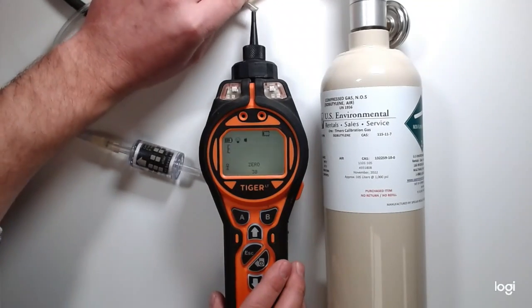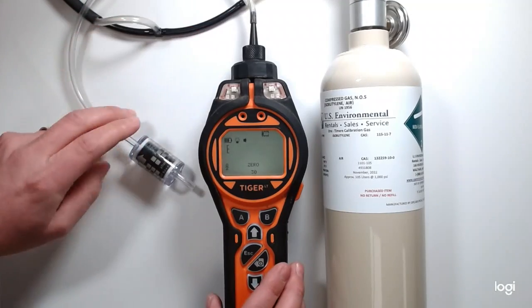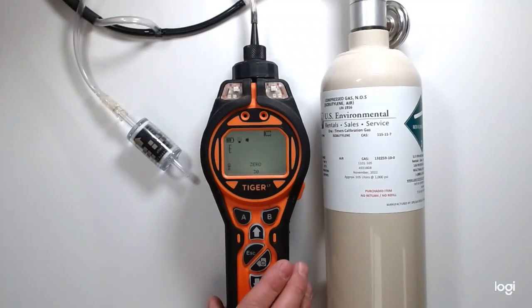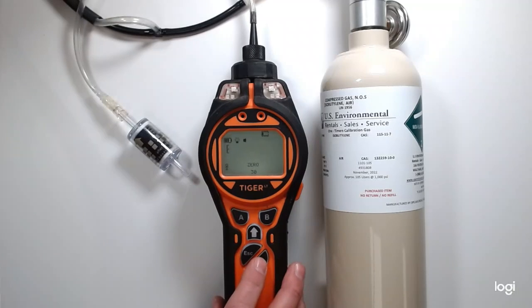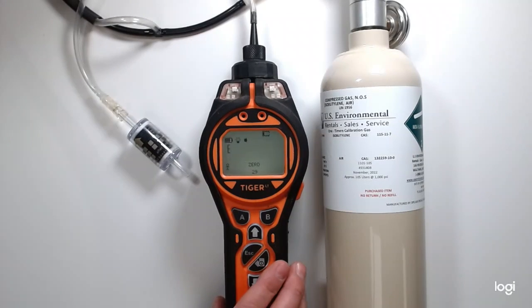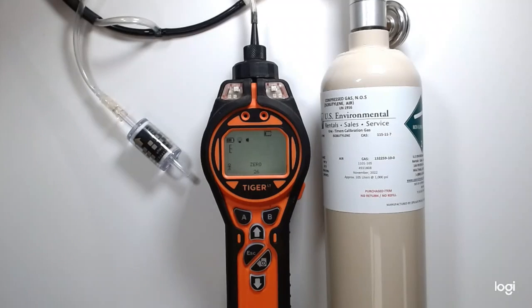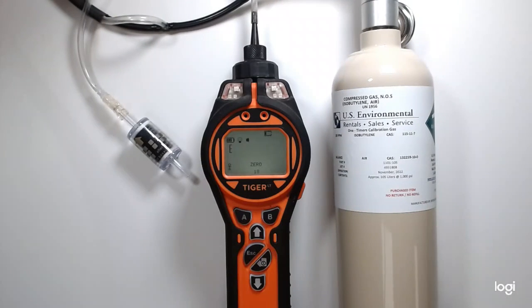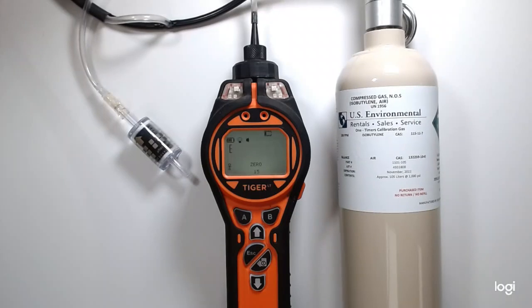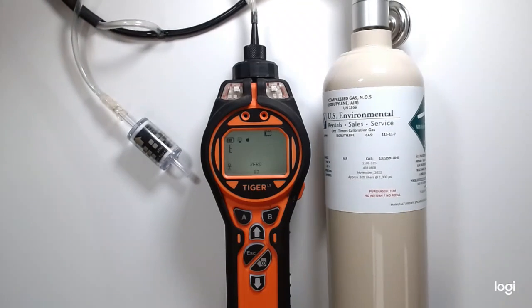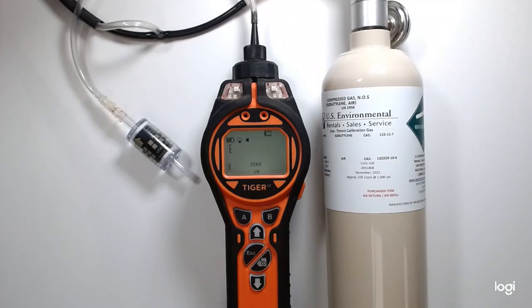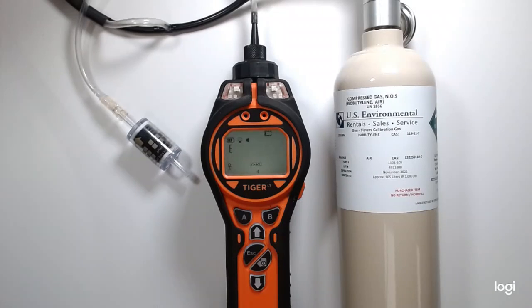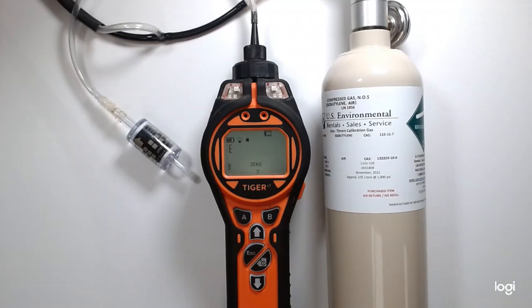Once we're there, we're going to use a carbon filter or zero grade air. In this video we're using carbon, and hit enter when we are all set. The unit will now count down from 30 seconds, and it will then ask for our span cal. On this instrument we're using 100 ppm isobutylene. If it were a PPB Tiger, we would use 10 ppm isobutylene, and if it was an 11.7 Tiger, we would do a multi-point span with 1,000.